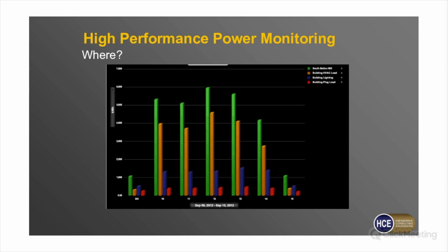This is a full week, so you can see on the weekends there's still some stuff going on. Some lights are still running on the first day, and then as you move, when all the people show up, it's all air conditioning load. Once you can track this week over week, you can start to see how weather's affecting you. You can make sure you're turning this stuff off on holidays. If you've got a 3-day or 4-day weekend scheduled, if you have somebody available, they can check and see, oh look, we didn't schedule the holiday—let's hurry and get that scheduled off. Maybe you can set some alerts so you get an alarm if it's a scheduled holiday and the kW reaches over a certain number, so somebody can make sure and schedule all the AC off.